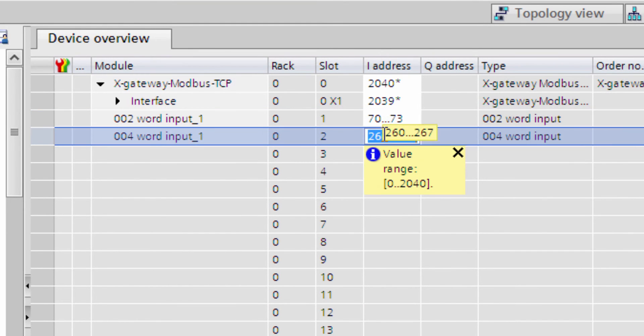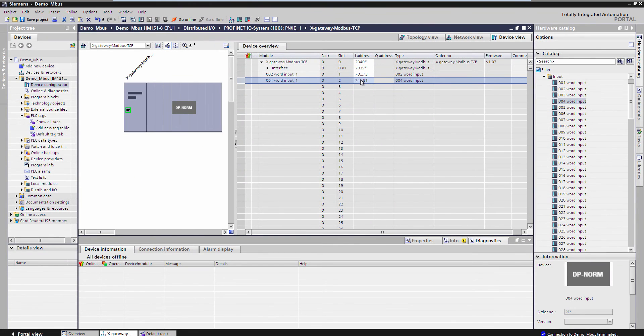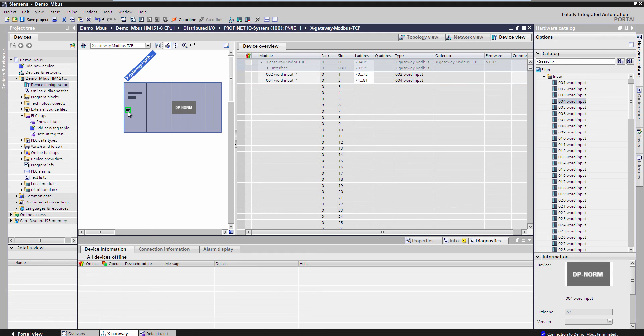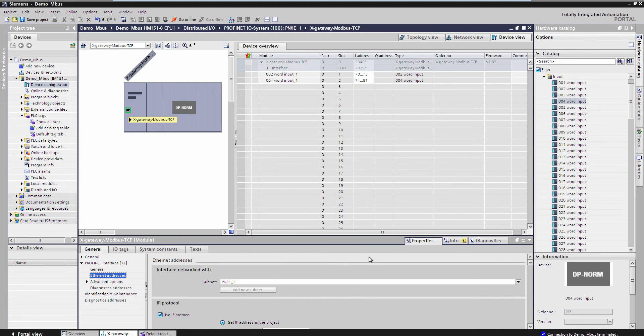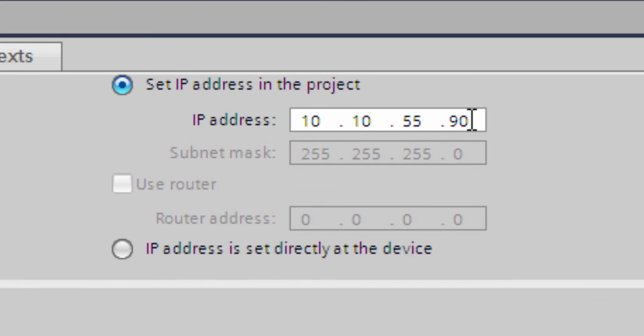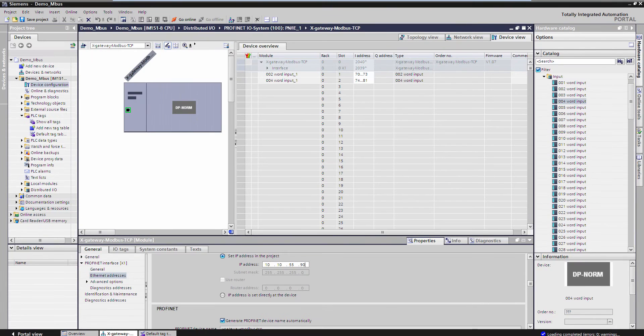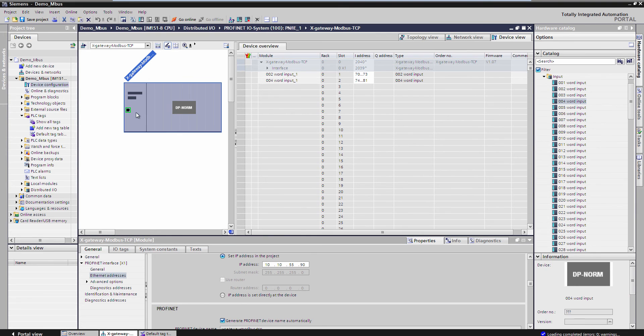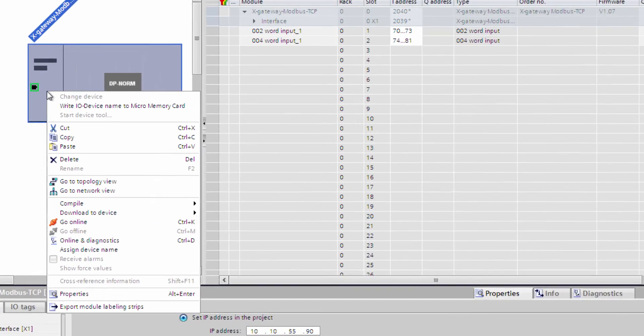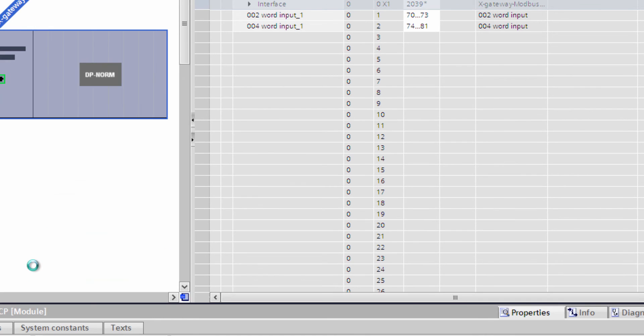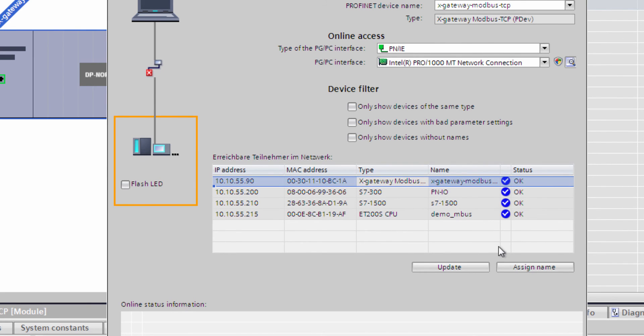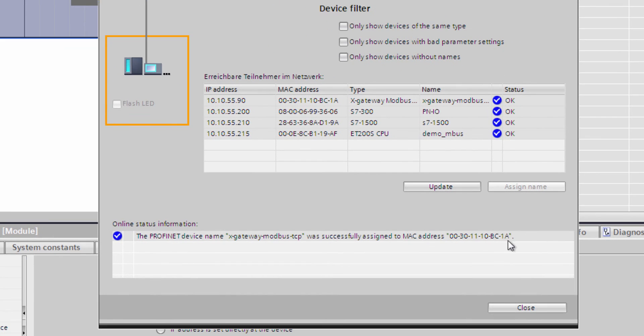I then decide which addresses I want the input to have in the PLC. In this example, we use 70 and 74. I also need to set the IP address for the x-gateway on the PROFINET network. I set this to be 10.10.55.90. Next, I need to assign a device name, which I do by right-clicking on the x-gateway and select Assign Device Name. Here I search for the available units and see that my x-gateway shows up. I select this and click Assign Name and then Close.